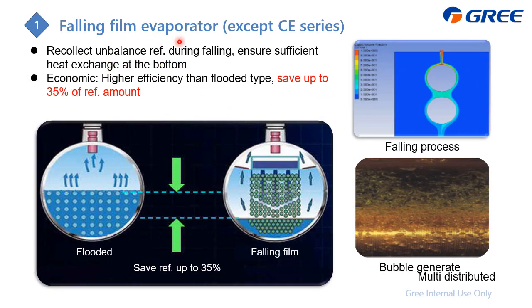First, we will talk about the evaporator. Our latest product also adopts this falling film technology. The falling film, just compare with the flooded type. For the flooded type, first I will explain how it works. You can see this blue area. It is actually the refrigerant, which means we put the liquid refrigerant just inside, and the water, which is the chilled water, just inside the tube. So the refrigerant absorbs heat, which cools down the water, and then the refrigerant itself will become gas, which flows upward, then flows into the compressor, and then the water will be chilled down, right?